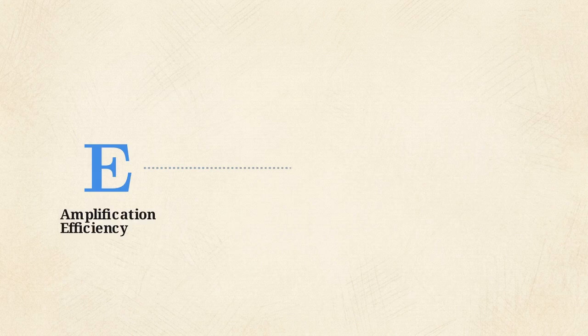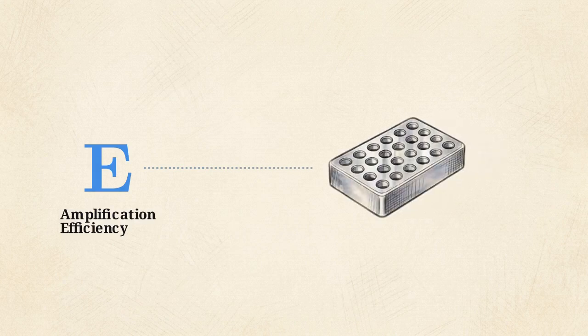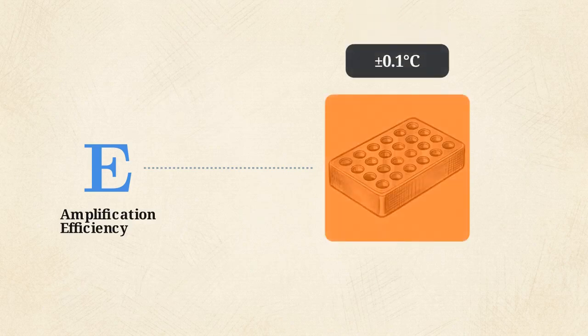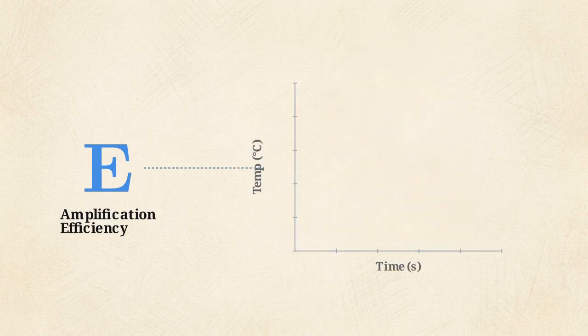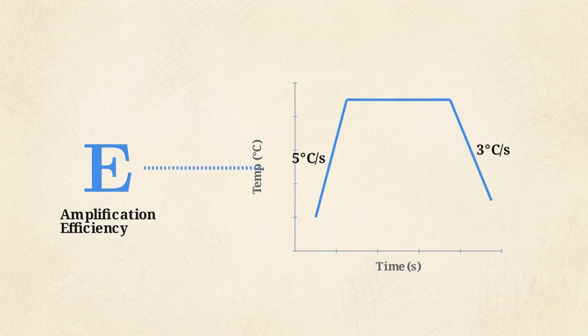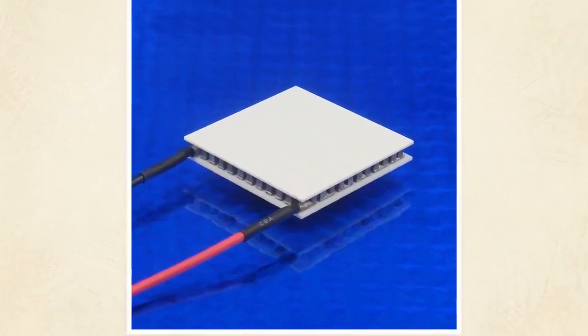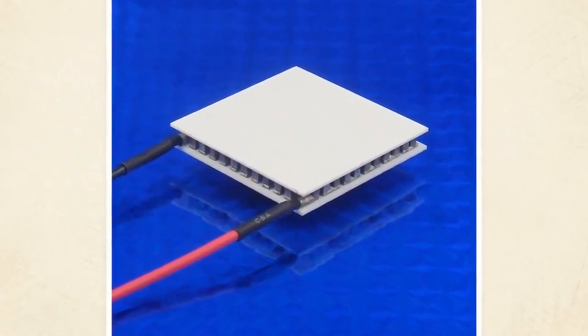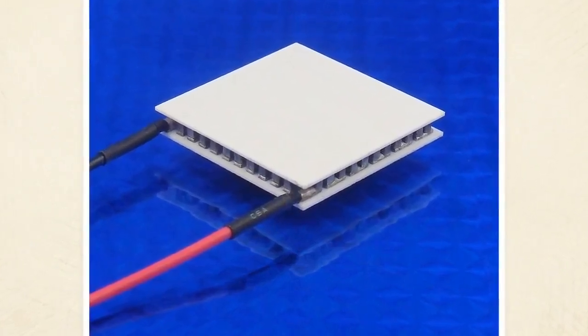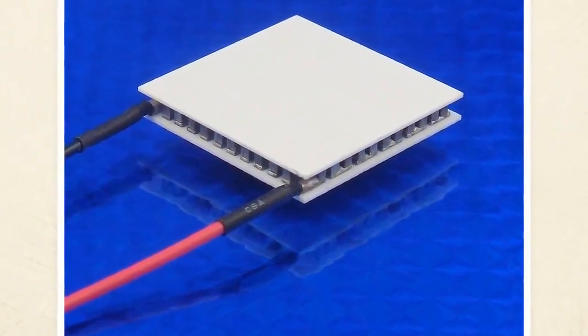The mathematical requirement for perfect amplification efficiency translates directly to extreme physical constraints on the thermal subsystem. The hardware must maintain a spatial uniformity of exactly plus or minus 0.1 degrees Celsius across the entire multi-target array simultaneously. To equalize the efficiency across all 18 target genes, the thermal block must execute aggressive ramp rates, heating at 5 degrees per second and cooling at 3 degrees per second. Generic heating elements cannot execute that profile without overshooting the target. The system requires high-end, custom Peltier microheaters to snap to temperature and hold it.